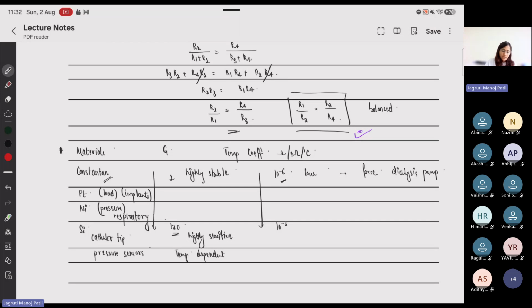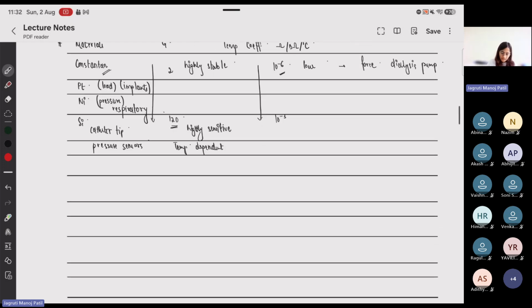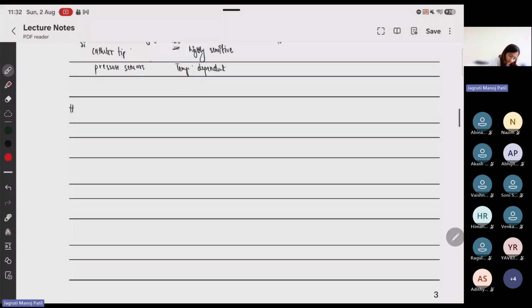So that was all about the basic types of materials you have, like strain gauges. There are also types of strain gauges: unbonded and bonded. In unbonded ones, you have a fixed arm and a movable arm. Because of this fixed and movable arm, energy loss is very low and the system becomes highly sensitive. So you can use them in catheters or needle-based systems, for angioplasty, small signal measurements, real-time measurements.